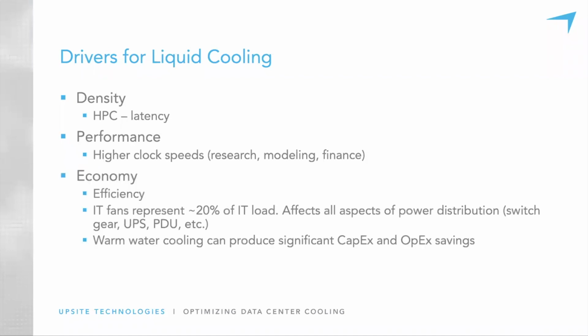And then economy. As most of you said, what's most important to you is reducing operating cost. There are very substantial efficiency benefits that can be realized by going to liquid cooling. One of them relates to the fans in the IT equipment. Approximately 20% of the load that goes through the critical power distribution system, the UPS, the PDUs, and into the server chassis, gets consumed by the fans in the servers.